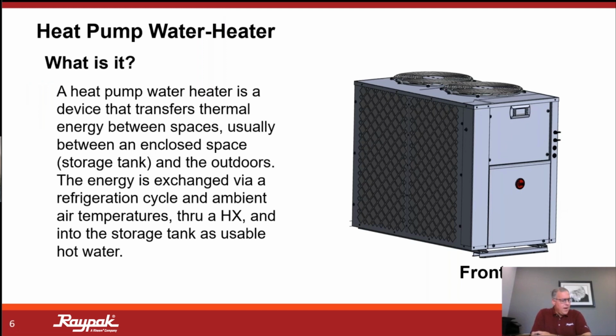I always like to start out with what is it? What is it we're talking about, and how does it work? And a heat pump water heater is really just a device that transfers heat from a space into a storage tank. So we're taking the ambient air temperature, we're extracting heat from it, we are rejecting that heat from a heat exchanger, and we're going to place that heat in a storage tank in the form of domestic water, hot, usable domestic water. At this time, this product is for domestic water heating only. Down the road, it very well may be that we have a different animal to work with for space heating, for hydronics, and those types of things. But at present, in this launch, it is for domestic water only.